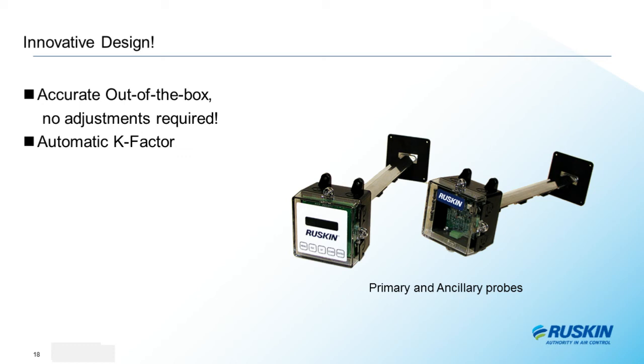If the air is passing through the plane of the air measurement station in two directions, then you really do have a problem. But for those installations where the air is only going one way, we have 1, 2, or 3-point automatic gain and offset built in to this product to compensate for less than ideal installation locations and non-linear airflows. Simply enable automatic K-factor correction and select how many points to use to make the reported airflow match test and balance measurements. It's that easy. Gain and offset is automatically calculated.